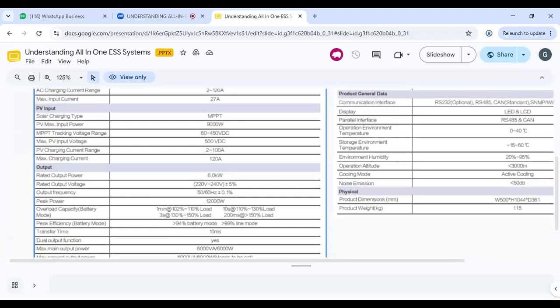Then the output capacity of the inverter is 6 kilowatts. The voltage is by default set to 230. If you want to bring it down to 220 for a reason, you can do that. You can set it up to 240 if you want. The frequency is 50 Hz. Because we know that some loads operate on 60 Hz, that's why it's flexible. You can change it to 60 Hz depending on the type of load you are powering, but generally the acceptable frequency here is 50 Hz.